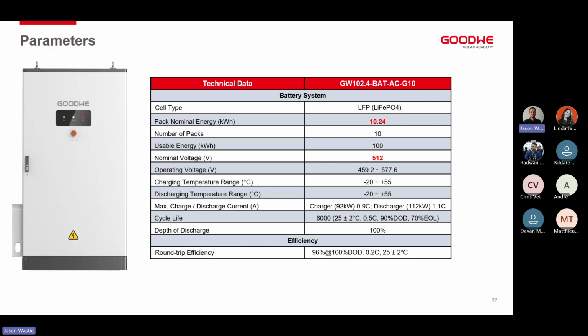It is a 0.9C charge and 1.1C discharge battery, which isn't an issue at all. We obviously get the maximum out of this battery permanently because we'll connect this to our 50 kilowatt inverter. This battery is also compatible with our 100 kilowatt ET series inverter, which is why we've got the 0.9C and 1.1C charge and discharge. The depth of discharge is 100%.